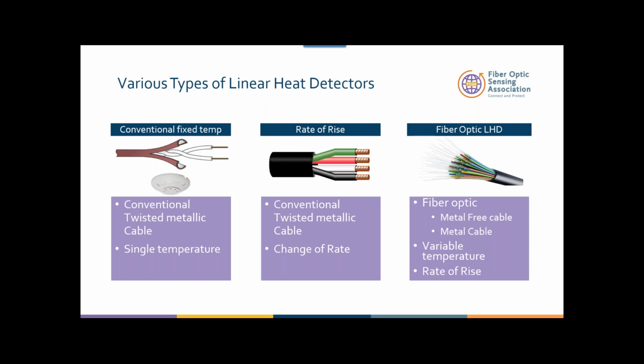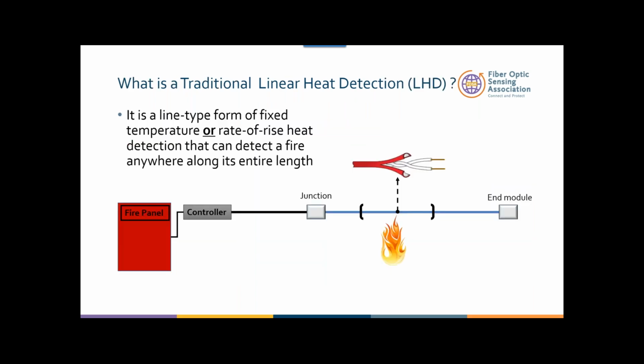The reason why we are here is to talk about fiber optic linear heat detection. This is very, very, very exciting for me. It's exciting for hopefully everybody in the audience. Fiber optic linear detection is a system where you eventually decide whether or not you're going to use a metal-free cable or a metal cable, variable temperature, and rate of rise. So you get a lot of flexibility in that. So what is a traditional linear heat detection? A traditional linear detection, as I said, is you get the temperature, you get a fire, and then it shorts itself, then you get an alarm.